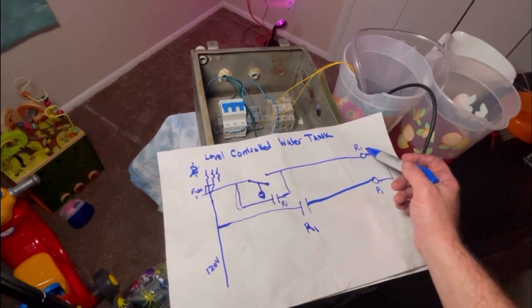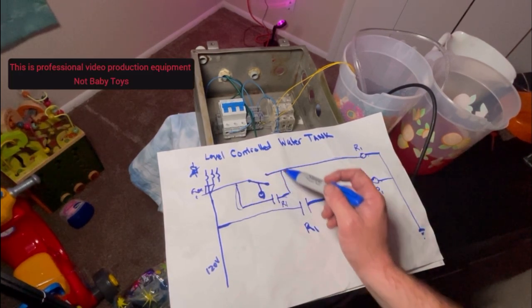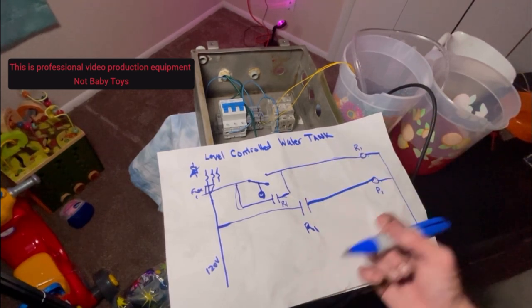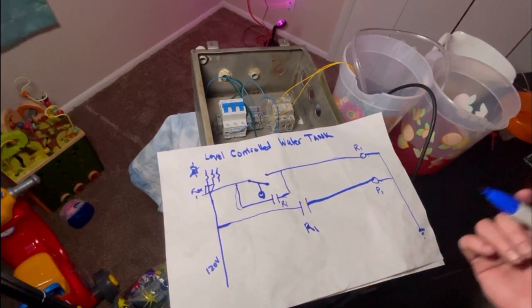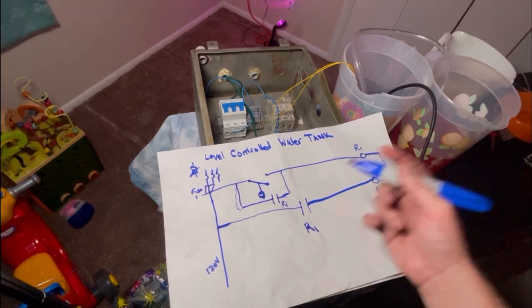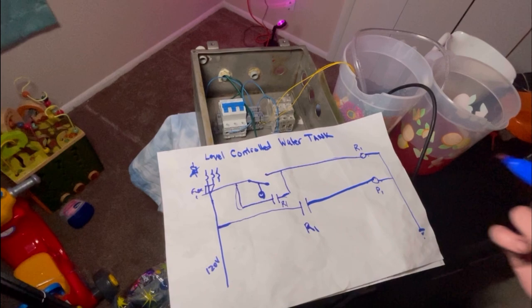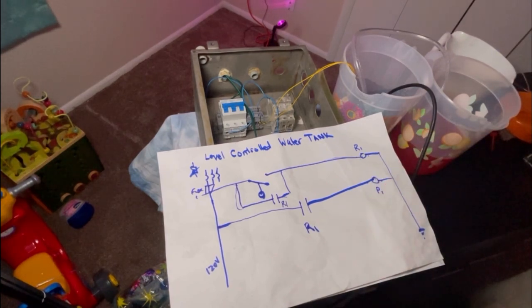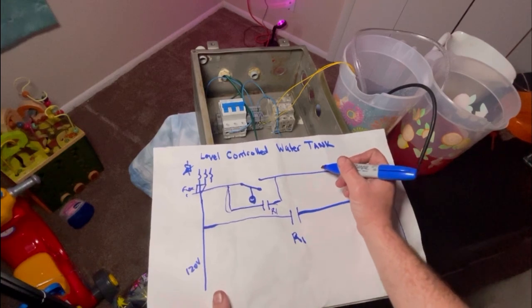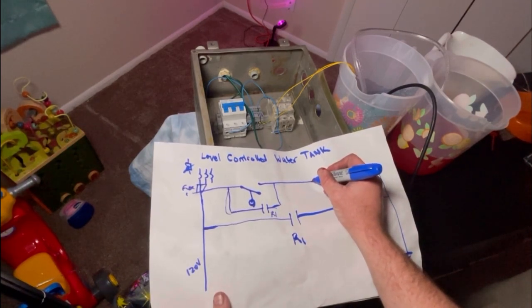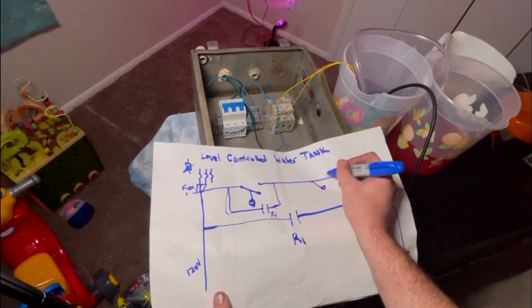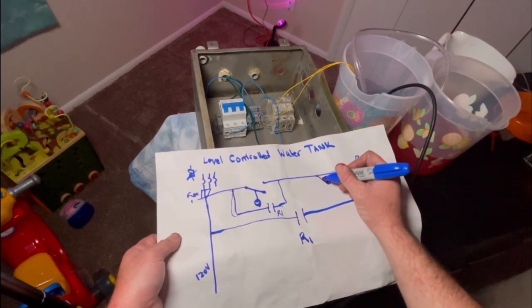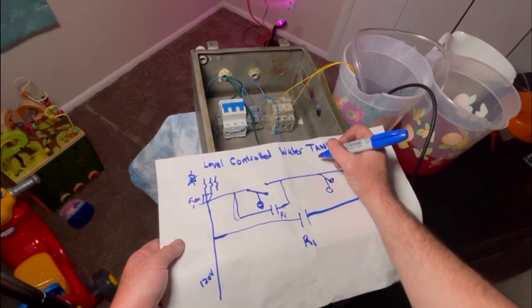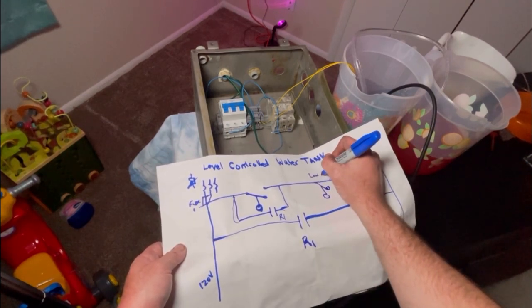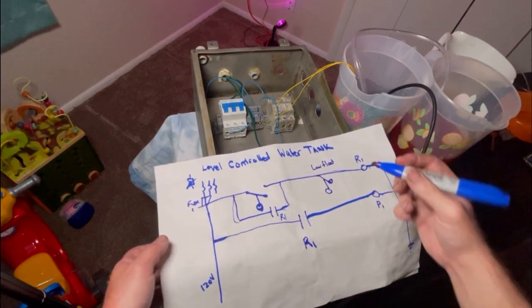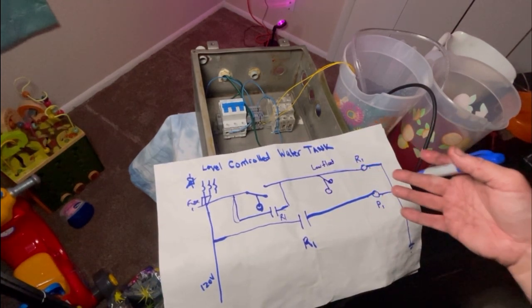So when relay 1 turns on, this circuit's going to become active. But we don't want it to just stay on forever. We need something to interrupt it. So we're going to put another float switch even lower in the tank. And when that float switch drops down, it's going to open up the circuit. So we're going to have another normally open. Ignore that. I don't have a magic marker eraser. We're going to have another normally open float switch. We'll call that the low float. So that thing's going to be hanging out towards the bottom of our tank, you know.